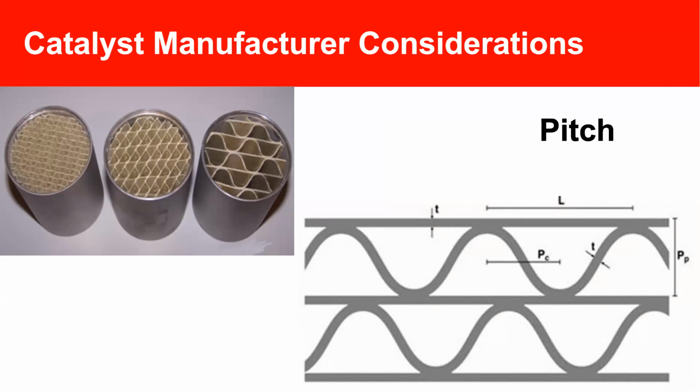In fact, in some of the refinery units that are burning natural gas, we intentionally use a larger pitch to help with some DP issues that could occur with refractory fiber. And more often than not on these units that were designed with 90-degree ductwork upstream, there is refractory fiber issues. So it's not unique to any individual unit. It's kind of seen across the board.